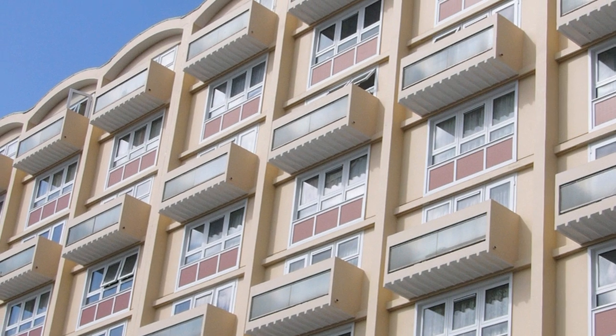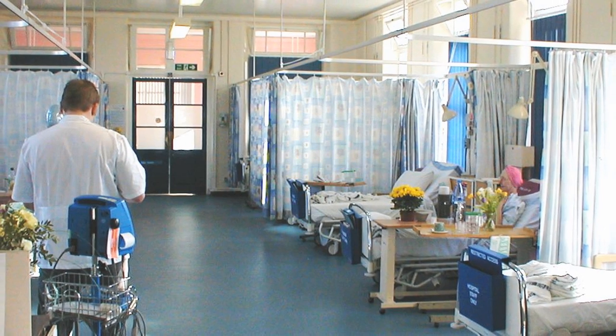District heating is not a new idea, and there are thousands of systems in the UK already. If you live in a block of flats, work in a hospital, or went to a large boarding school, you may have already benefited from heat that was delivered by a district heating system. In such situations, there's very often a central boiler house or boiler room containing one or more boilers that run on coal, oil, or gas.